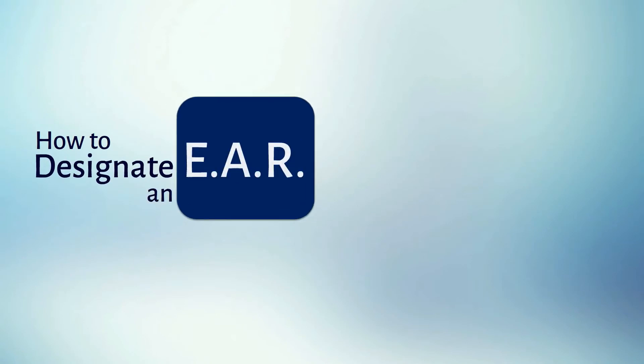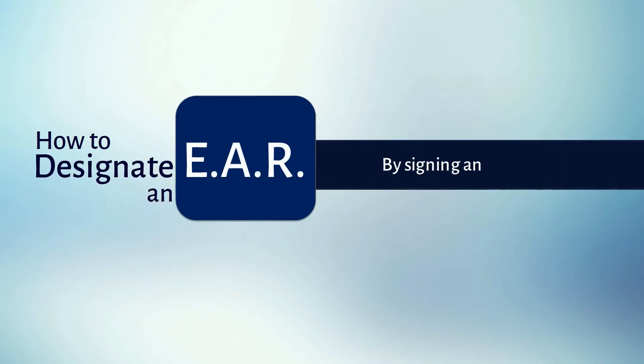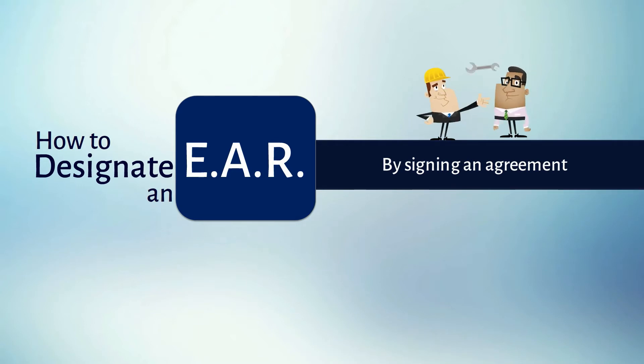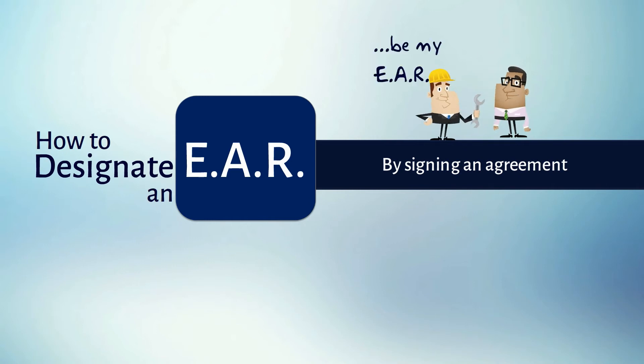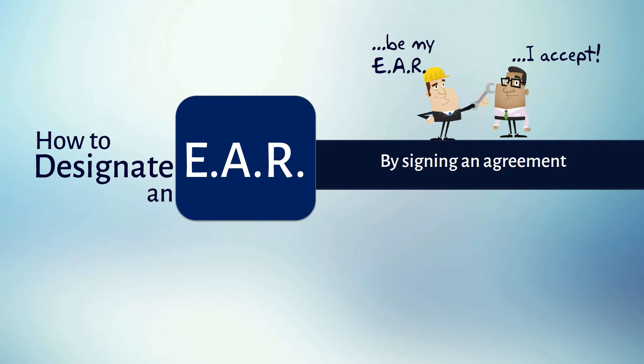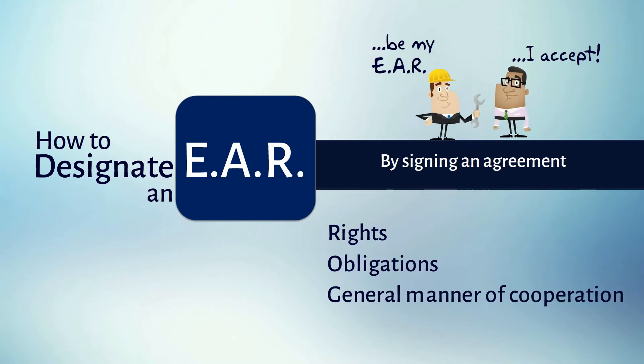To designate an EAR, the manufacturer and the EAR sign an agreement which essentially says: 1. Manufacturer, you will be my authorized representative in Europe, and 2. European Authorized Representative, I accept to be your European Authorized Representative. In addition to the agreement, you will need to mention the rights and obligations of each party and the general manner of cooperation.